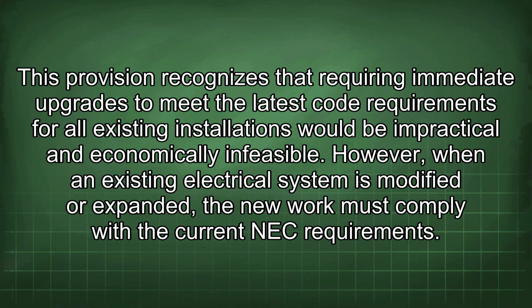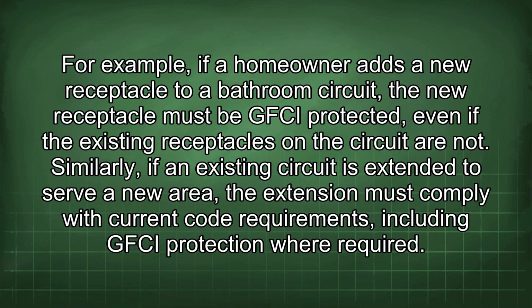and economically infeasible. However, when an existing electrical system is modified or expanded, the new work must comply with the current NEC requirements. For example, if a homeowner adds a new receptacle to a bathroom circuit, the new receptacle must be GFCI protected, even if the existing receptacles on the circuit are not. Similarly, if an existing circuit is extended to serve a new area, the extension must comply with current code requirements, including GFCI protection where required.